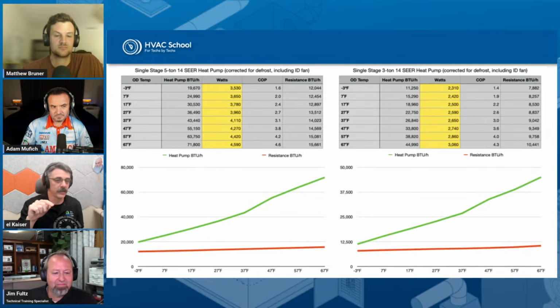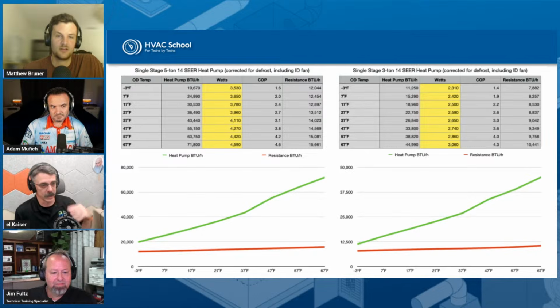But the other piece to this is that this particular manufacturer I got the data from actually corrects for the defrost. They take that defrost time out of there, and there's some more information we'll show later on about how that works. You can kind of see a jump up around 47. We see some things level off there in performance because that's about where we quit defrosting. And then when we swing down below 27, when we get colder outside, we actually get slightly less defrost cycles because we don't have a large amount of moisture in the air, because the air is then below freezing. As opposed to just the coil being below freezing and the air still being above freezing.